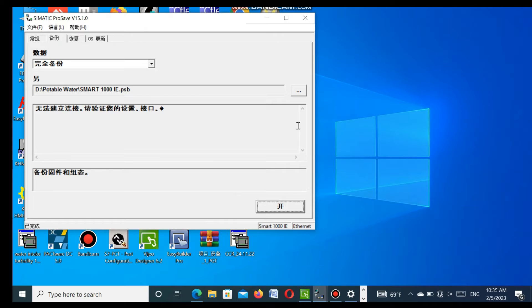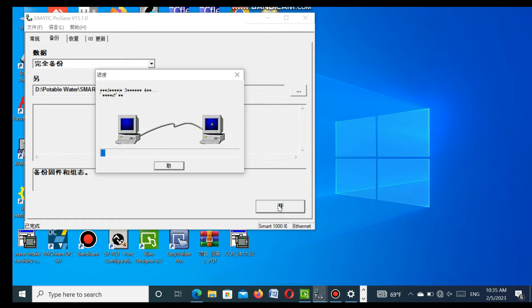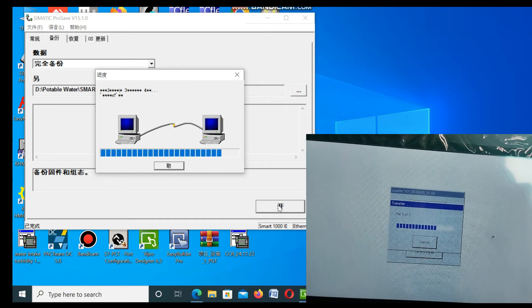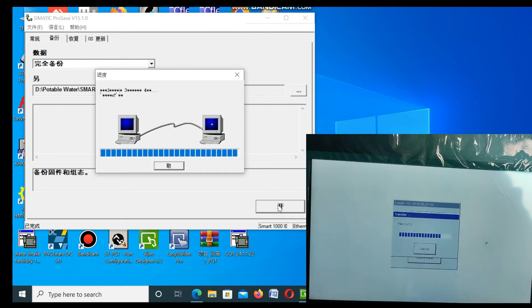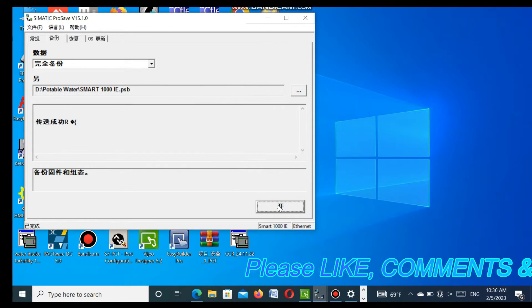Then, go to the SIMATIC ProSave software and press the upload button. Press upload — then connect. That means, communication is established between the HMI and the laptop, and the program is uploading step by step. You have to remember that the IP address of the HMI and the laptop must be the same series — that means 192.168.0 or 1. If the SMI is 0, you put 0; if 1, it is 1. Here, the program is uploading, and on the right side corner, I am showing the condition of the SMI — it is also showing that the program is uploading or transferring. Upload is completed.